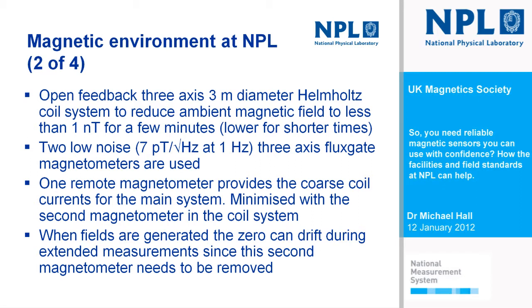So during that time that we're applying our fields, by measuring the current through the calibrated 1 meter diameter Helmholtz coil, the ambient can drift slightly. So there's always a possibility of having this drift occurring, which will appear as a variation in the background and ultimately could affect the uncertainty of our measurement. So we want to close that feedback, and in doing so that'll give us more stable field readings and lower the noise that we have on the magnetic field levels that we generate.